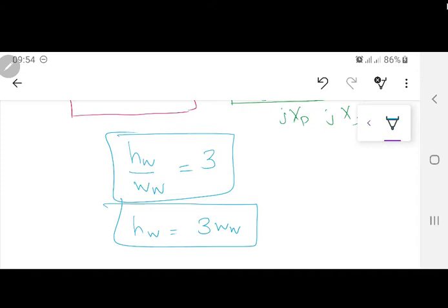Supposing, just for example. Now 1000 turns, maybe they don't fit in the whole height. So you will have to do 2 layers. Now when you are going to do 2 layers, you cannot do something like this. You started from here, this was the first layer done, and then you have to go to the second layer. Now the second layer should reach the end from where you started, because you can't have it uneven. And this unevenness will be more severe if you are having a low voltage winding done first, because on the low voltage winding you have to keep the high voltage winding. So technically the layers should be uniform.